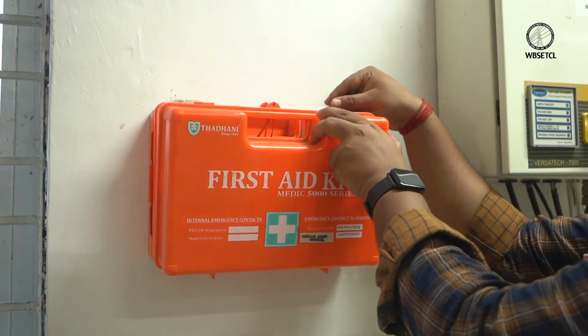We monitor electrical parameters round the clock like voltage, load, frequency, etc., along with recording of daily readings of circuit breaker gas pressure, energy meter reading, LA counter reading, etc. Safety is considered as one of the most important parameters at the site.